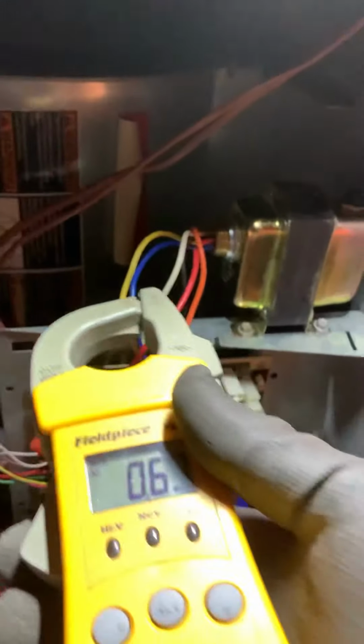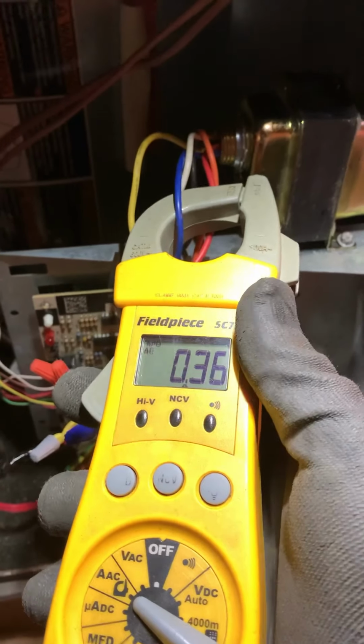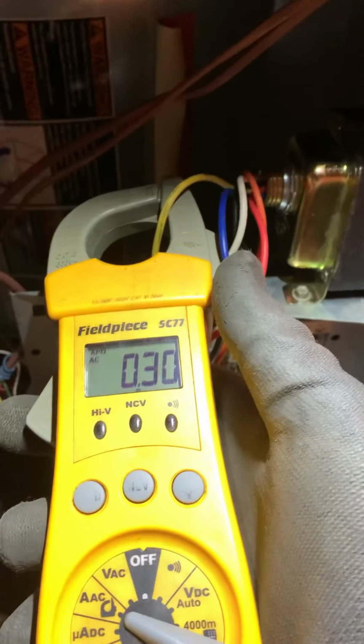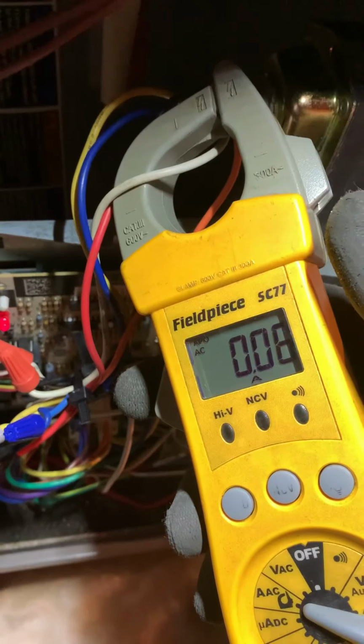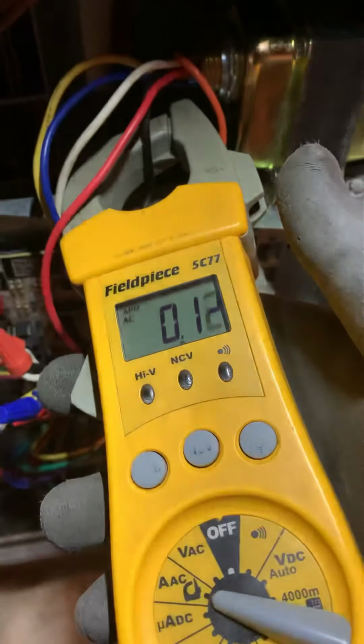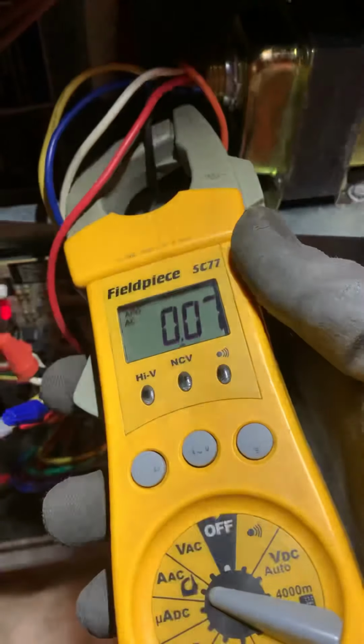All right, now quickly what I want to do is take an amp reading. 0.3 amps on blue, 0.3 amps on yellow. Sorry guys, hold on. Sorry about that. And on white there's 0.07. On black, 0.06. So the majority of the amperage is on the secondary, which is 0.3, which should be 100% fine.